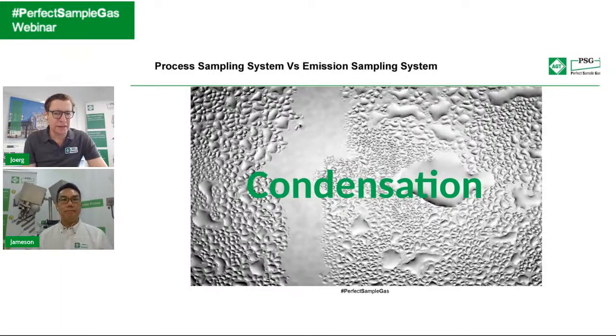Depending on the CEM emission, the emission monitoring we are talking about here, the temperatures of the chimney or the sampling or tapping point are not that high. So maybe that could also be a reason that the chance for condensation could be higher compared to the process measurement. Is this something you would agree on?